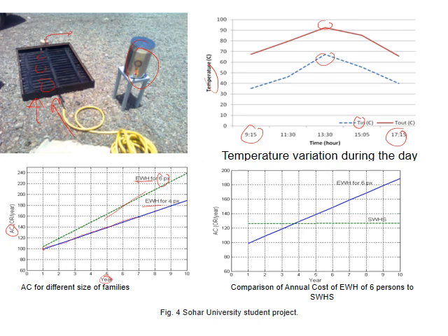But if we compare a 6 persons electrical water heater with a 6 persons solar water heater, the solar water heater, the green one here, is constant through time. Its cost will not change. Once we pay it, that's it, done. While the electrical water heater is cheaper at the beginning when we buy it, but with time, after another 3 to 4 years, its cost starts to be over that of the solar water heater. Why? Because we are paying for electricity, and this is added to the total cost.